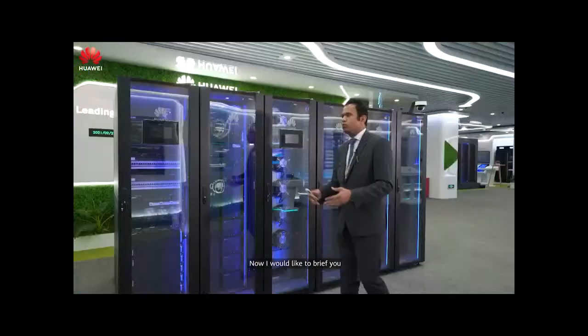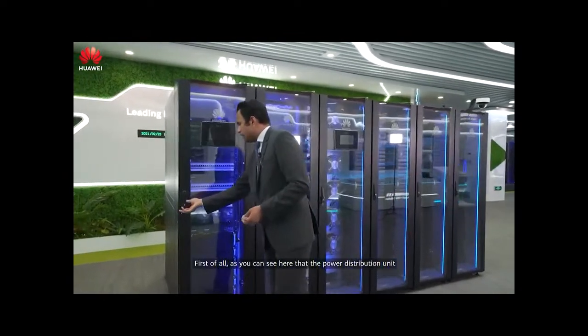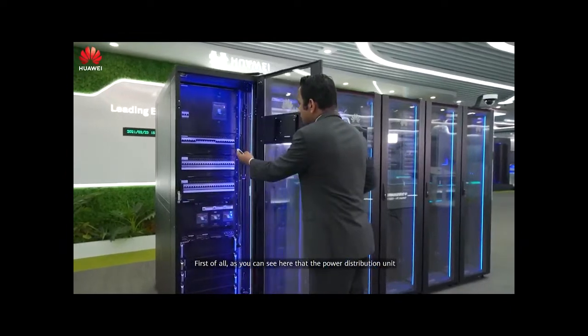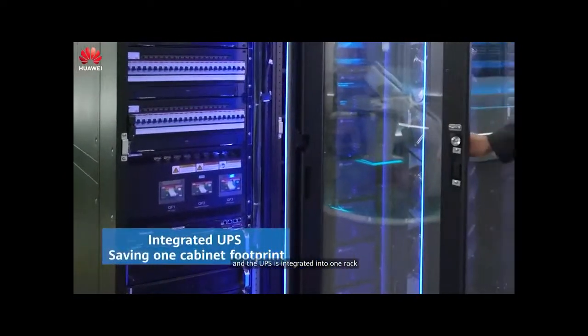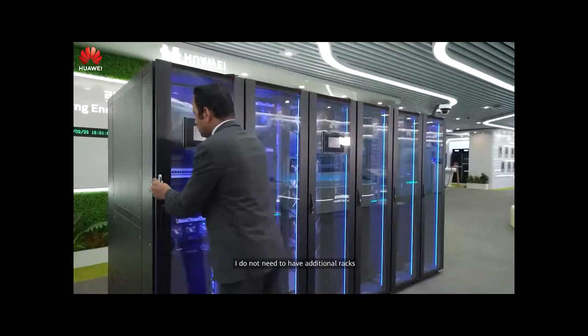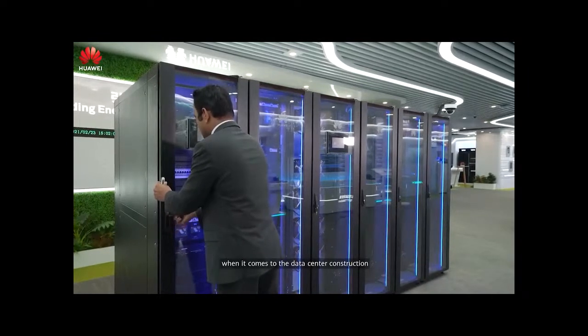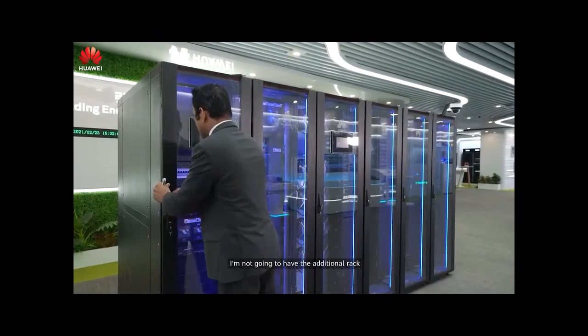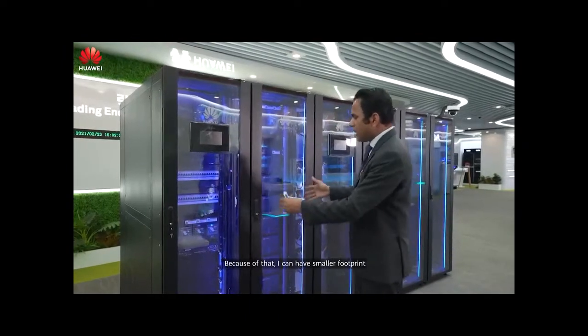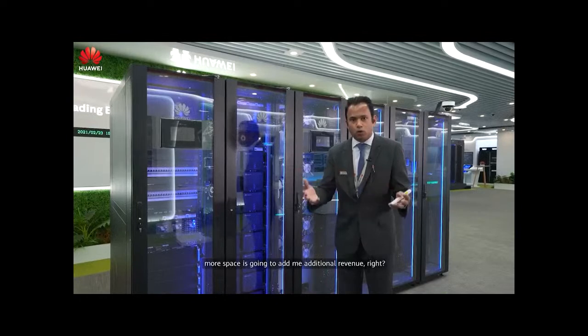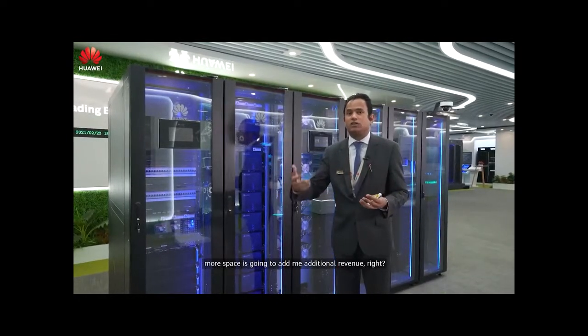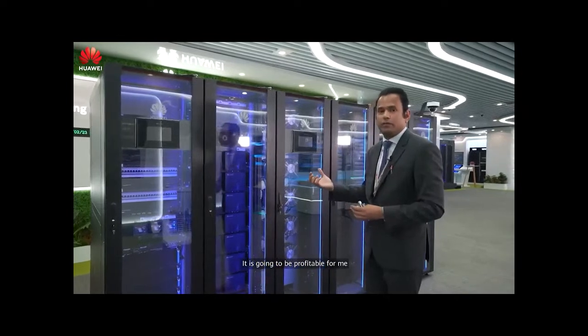Now I would like to brief you on some key highlights of Fusion Module 2000. First, the power distribution unit and the UPS are integrated into one rack, so I don't need an additional rack for data center construction. Because of that, I get a smaller footprint and can allocate more space for the IT rack. In a co-located data center, more space adds additional revenue, making it more profitable.